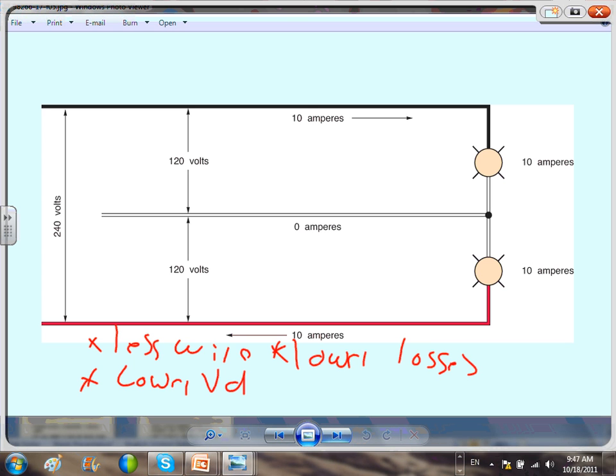Now, less wire, you guys can see that this is less wire, right? Less wire, you can tell that's less wire. Less voltage drop, I will remind you guys, voltage drop equals K-I-L over CM. Now, what's the voltage that I'm using in a multi-wire branch circuit? What's the voltage that I'm using? The voltage that I'm using in multi-wire is the 240, right? Here's my 240. And the losses are only in this cable and this cable.